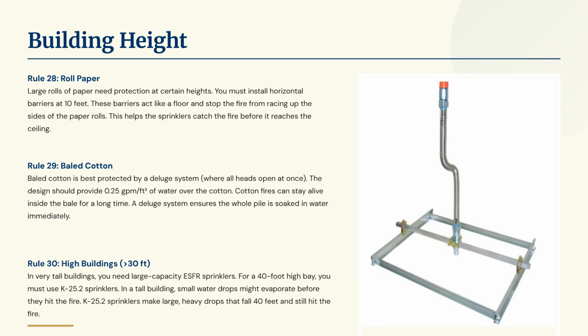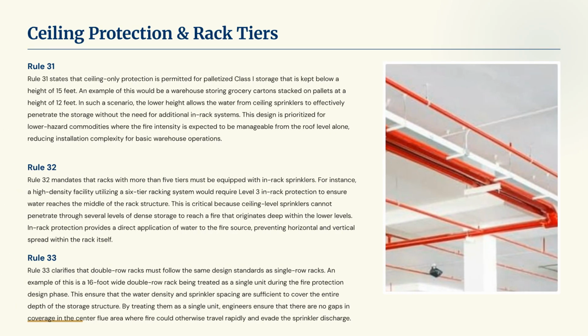Rule 29 recommends a deluge system with 0.25 GPM per square foot for baled cotton. Rule 30 specifies K25.2 ESFR sprinklers for buildings over 30 feet high. Rule 31 allows ceiling-only protection for Class 1 storage below 15 feet. Rule 32 mandates in-rack sprinklers for racks with more than 5 tiers.